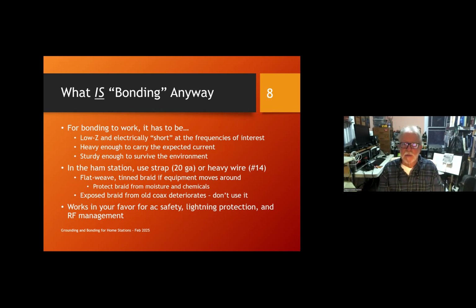And the higher in frequency you go, the shorter the wavelength gets, and the harder it is to keep these connections short. The bonding conductor also has to be heavy enough to carry the expected current. If we're talking about AC safety, and you want to carry the short circuit so that your protective devices remove power, then that bonding conductor has to be heavy enough to carry a short circuit current. So if you have a 20 amp circuit, it has to be at least able to carry 20 amps. If we're talking about lightning protection, like outside or at a tower base, and you might get hit by a kiloamp or higher current, then you have to have really heavy conductors.